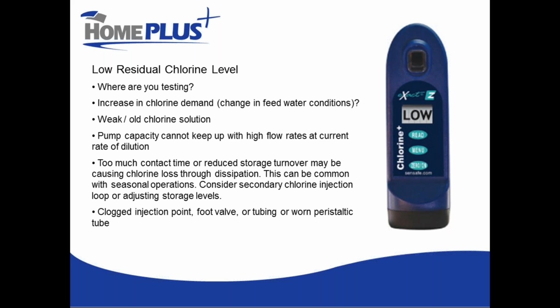The injection point is the point where the chlorine injects into your water pipe. That little point, especially if you have iron in your water, is very prone to getting deposits built up on the end of it or around it. So you should pull out that injection point and clean it periodically.